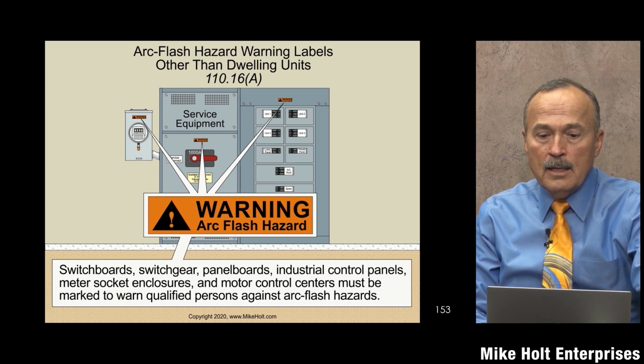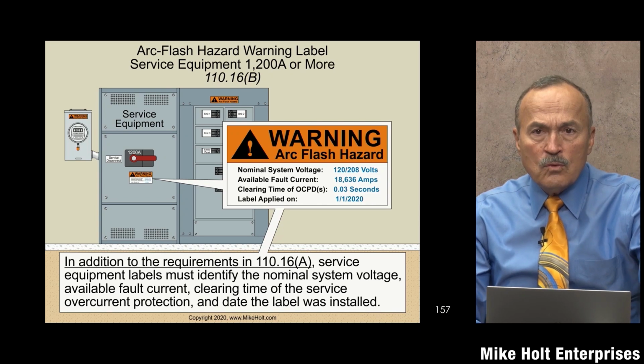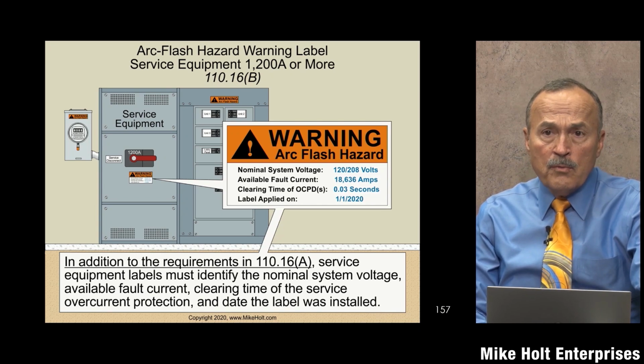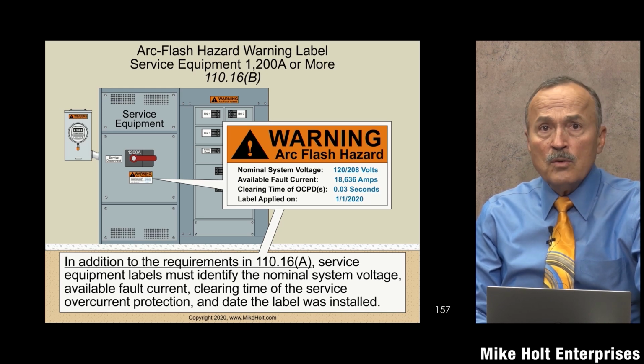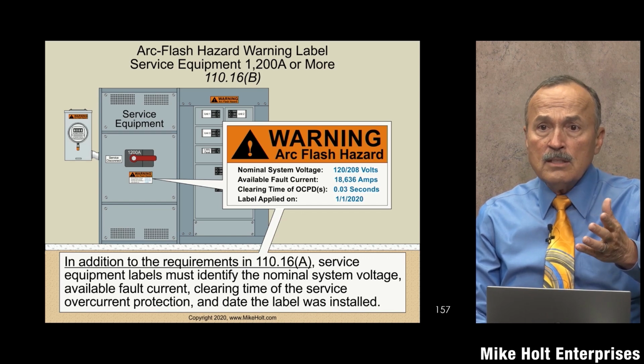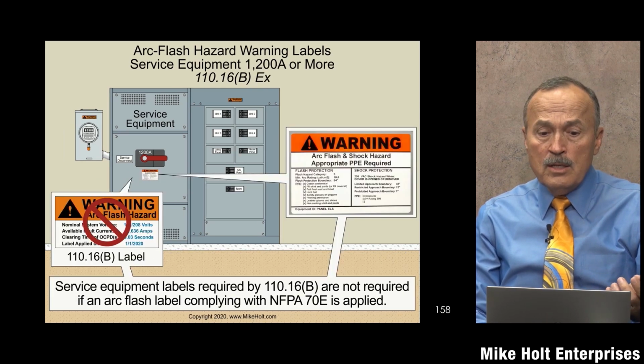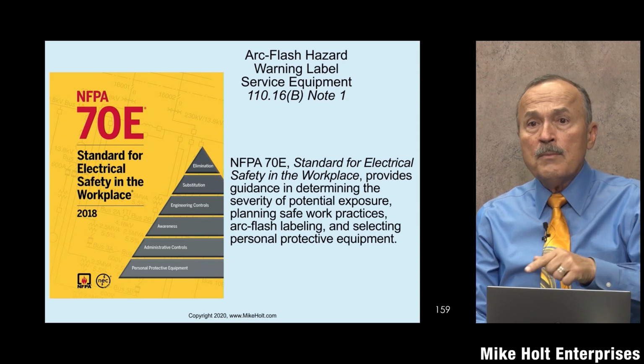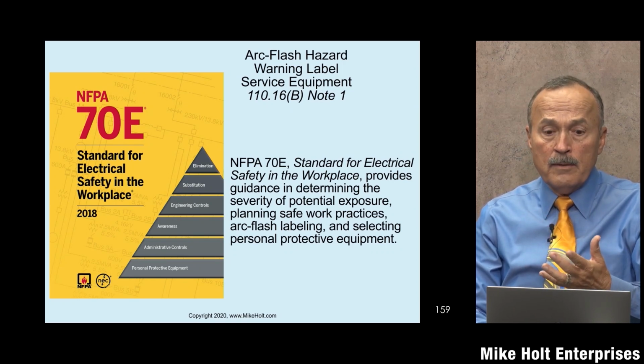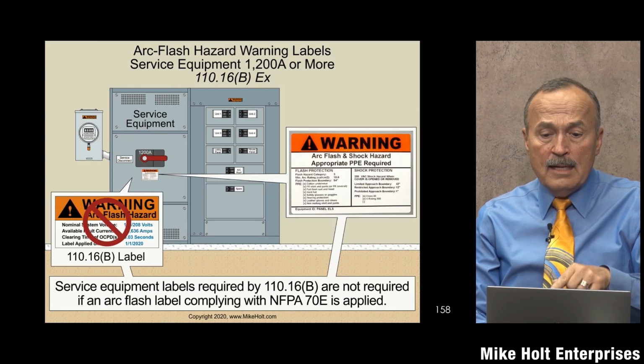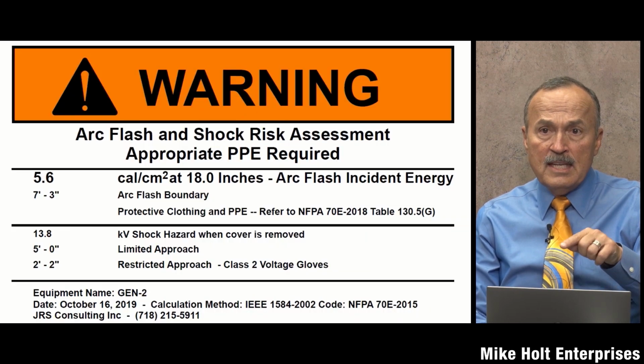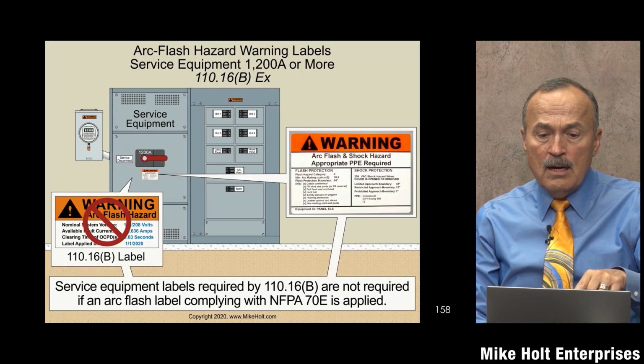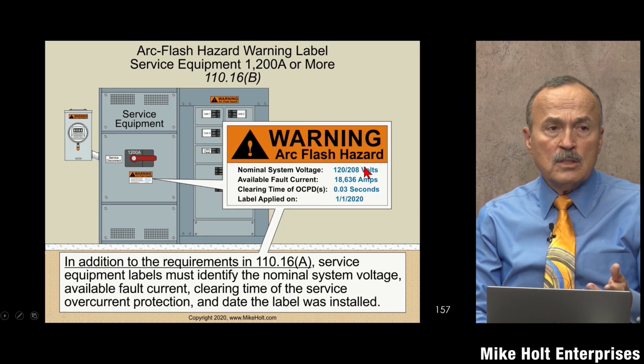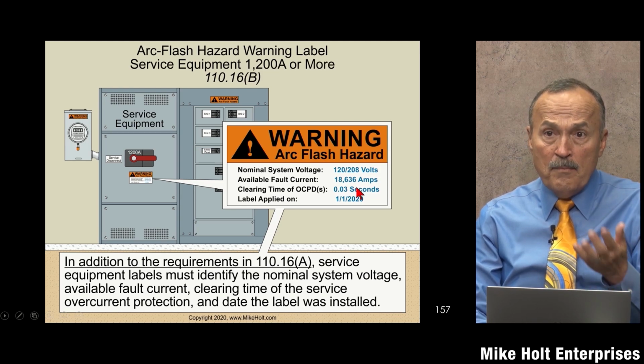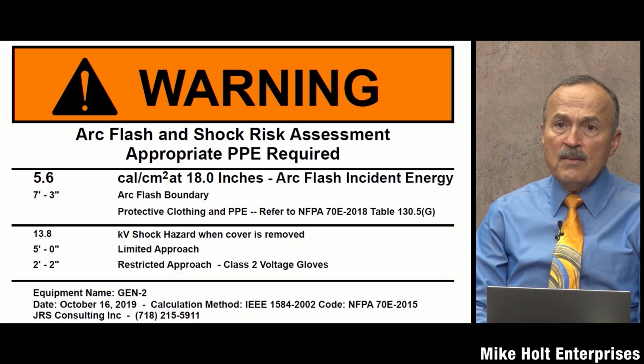No. And then (B) says if it's service equipment 1,200 amperes or more, then we want to have information: the nominal system voltage, the available fault current, the clearing time, and the date of that study. With that information, we can go to 70E, go to a table, and find what kind of PPE we should wear to work in there. Correct. But if you put an NFPA 70E label, then I don't have to do the calculation and show the nominal system voltage and the available fault, because we have all the information we need on the NFPA 70E label. Correct.